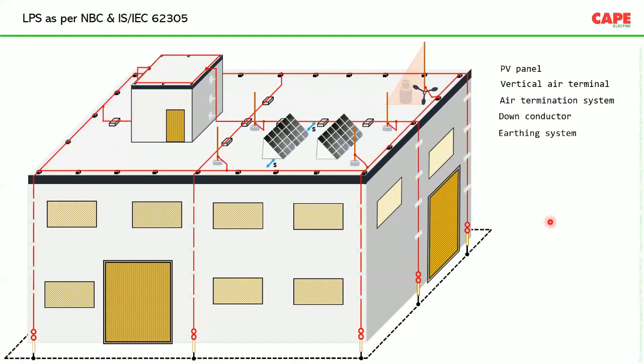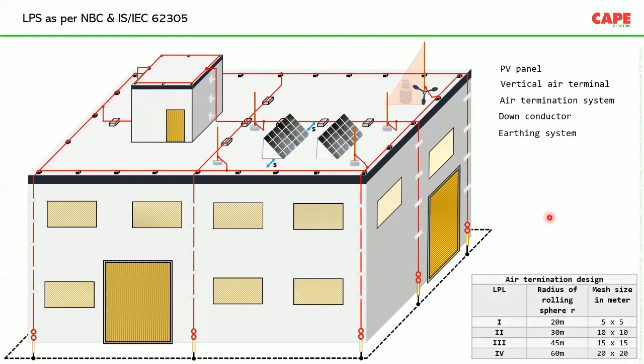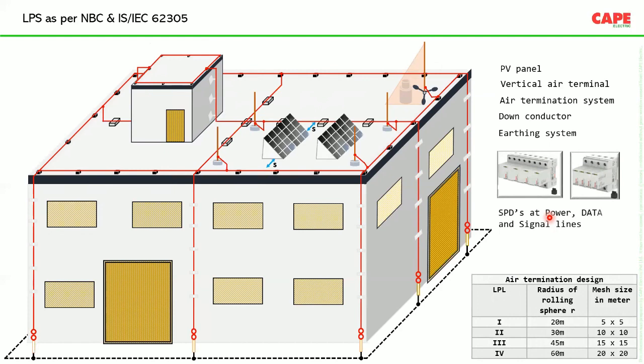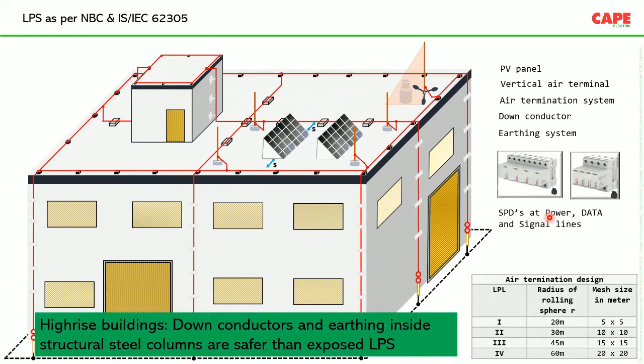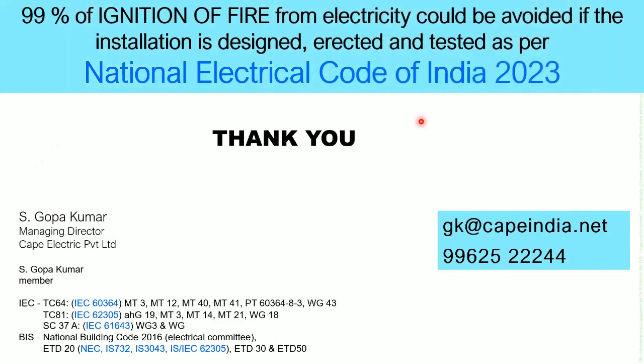Lightning protection must be carried out as per IS IEC 62305. Especially in hospitals, you must follow this particular standard, because the electromagnetics of the lightning can damage your electronic equipment. Now, only a properly or well designed and installed lightning protection can protect your electronic appliances. So with this, I would like to stop today's presentation.